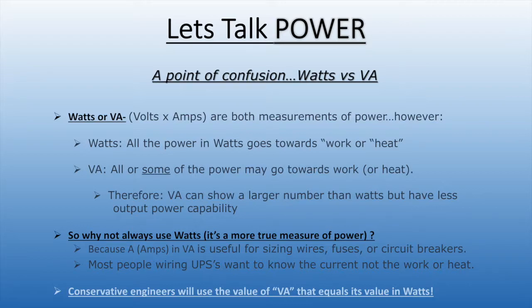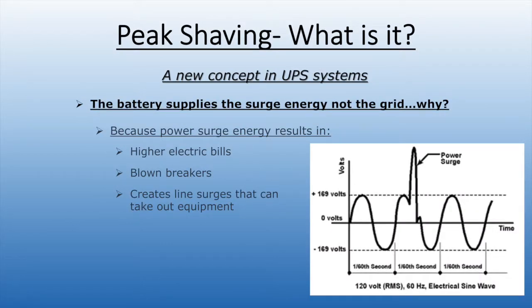Peak shaving is another feature found in UPS systems. It smooths out the power taken from the grid. As shown in the diagram, surges get pulled from the grid when hard drives and servers all power up or demand energy at the same time, which can result in higher electric bills since companies charge for peaks, not average power. Peak shaving works by having the battery supply power during those peaks, then slowly taking it back once the peaks are gone, avoiding higher electric bills.